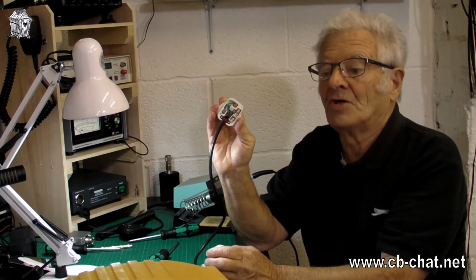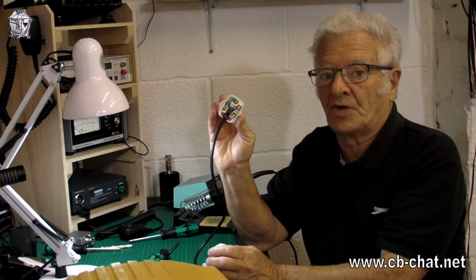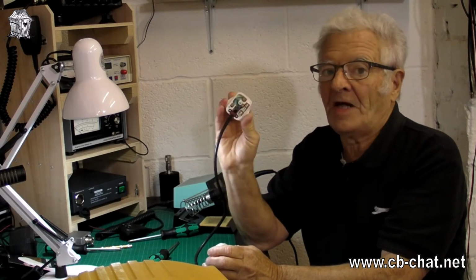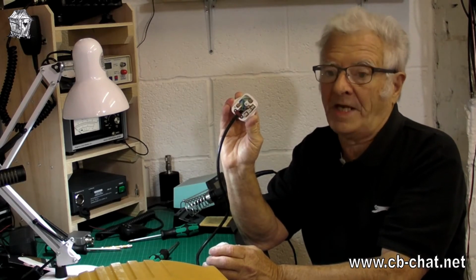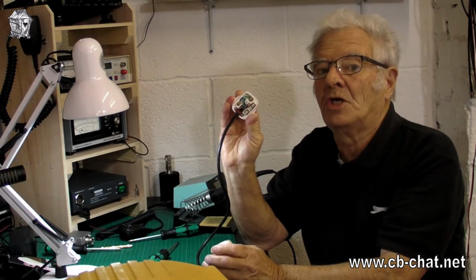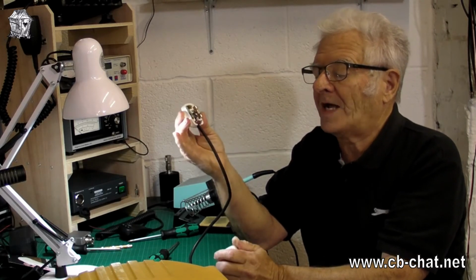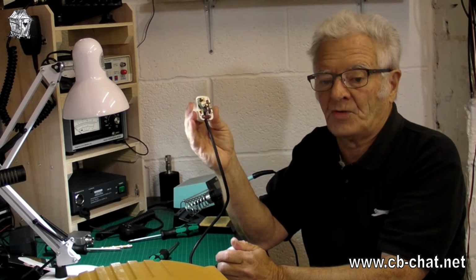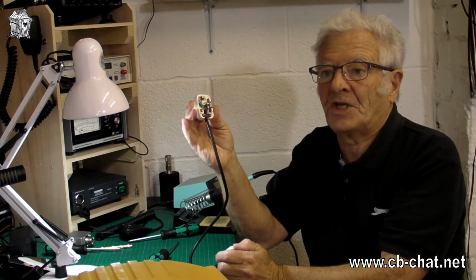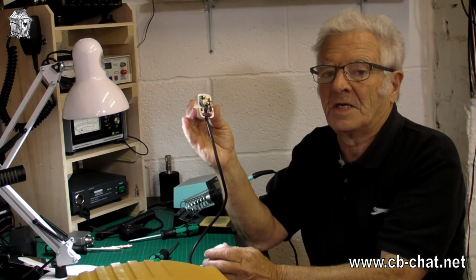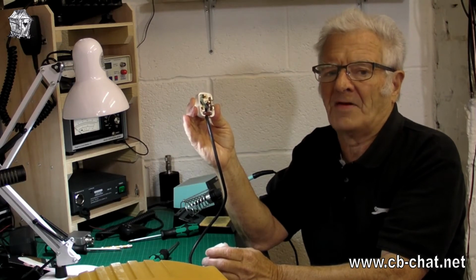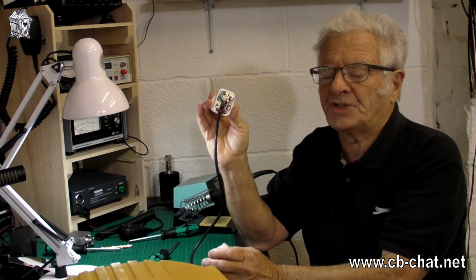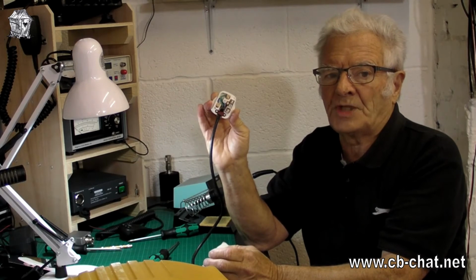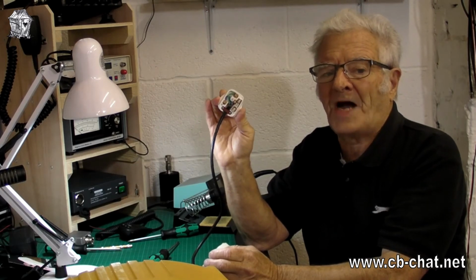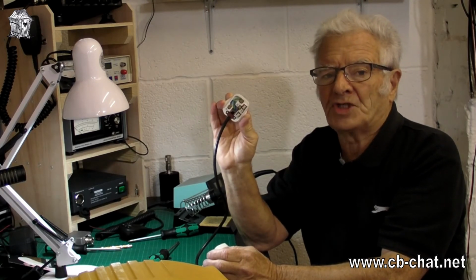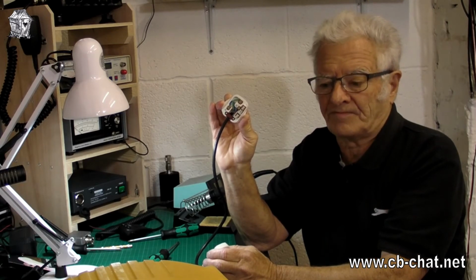But rules and regulations, more than my job's worth, mister. That is a failure. Now you won't believe this. This is absolute lunacy. But with PAT testing, you've got to put in a 13 amp fuse, an 8 amp fuse, is it 13, 8, 3, and that's it. Or is it a 5? I forget now. But the lowest you can put in is a 3 amp. You don't use anything smaller than a 3 amp. In the PAT testing world, fuses smaller than 3 amps don't exist.